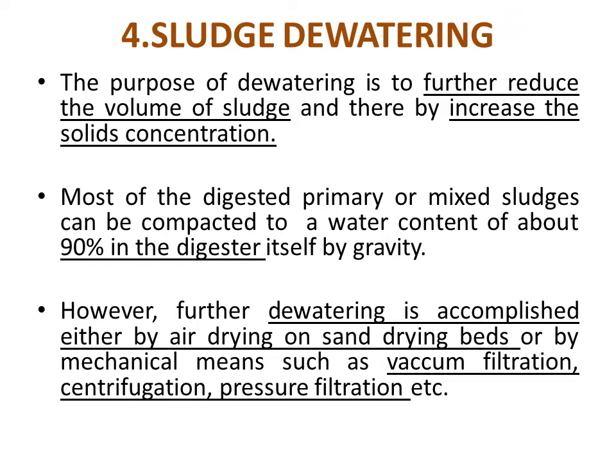Further de-watering is accomplished either by air drying on sand drying beds or by mechanical means such as vacuum filtration, centrifugation, or pressure filtration. The de-watering of concentrated sludge is commonly done by a continuous centrifugal process. In this process, the outer casing of a centrifuge contains a revolving solid bowl with a screw conveyor rotating at a slow speed. Sludge enters through the hub of the conveyor, and centrifugal force causes the solids to deposit on the walls of the bowl, from where they can be removed.